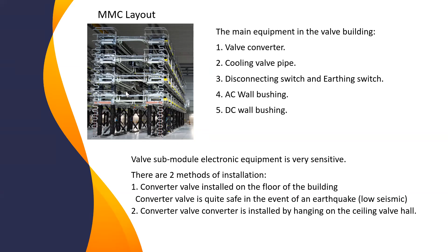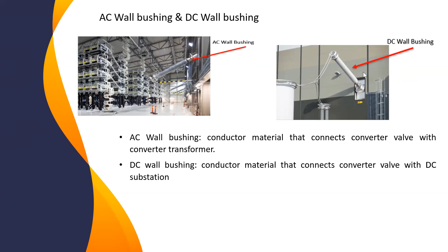So when we are talking about AC wall bushing, this is an example of AC wall bushing. What is AC wall bushing? This is the valve. The conductor to connect to the transformer, the converter transformer, we call it AC wall bushing. The same here, DC wall bushing is the connection on the other side: here AC, and on the other side we have DC. The connection of the conductor between the valve and the DC substation, we call DC wall bushing. This is an example of the connection from the valve to the DC smoothing reactor, where we use DC wall bushing.